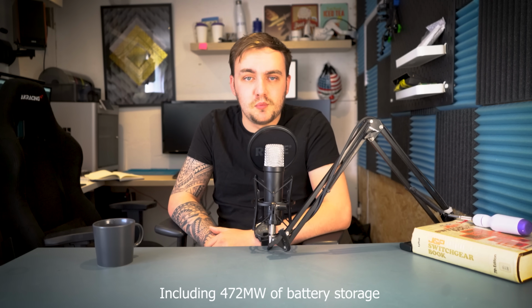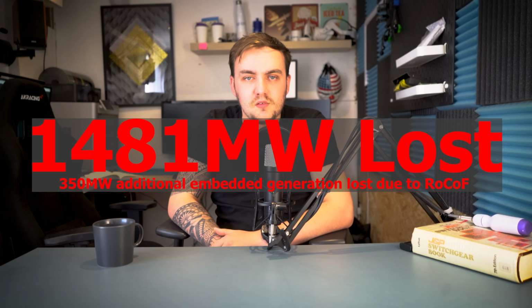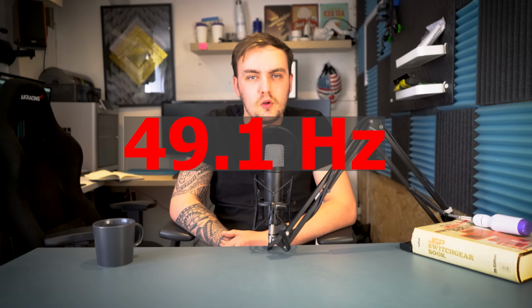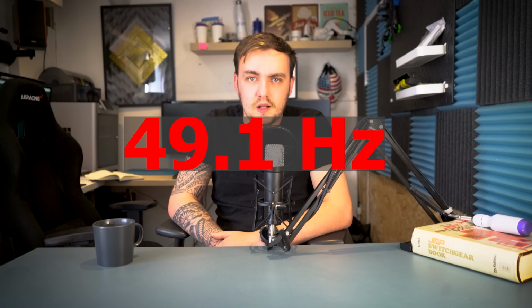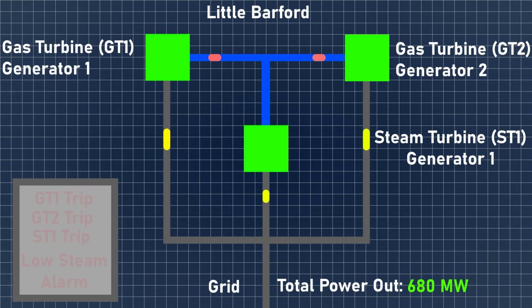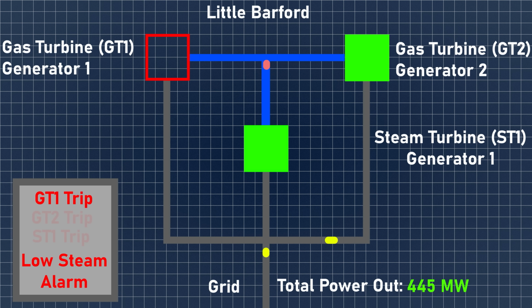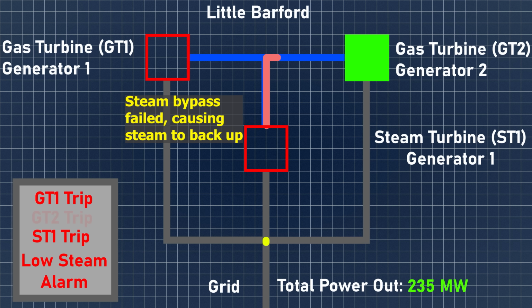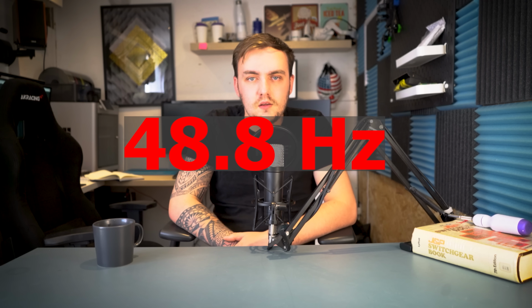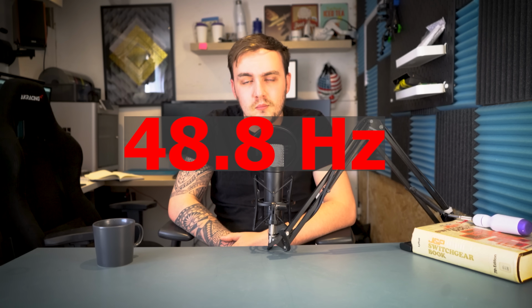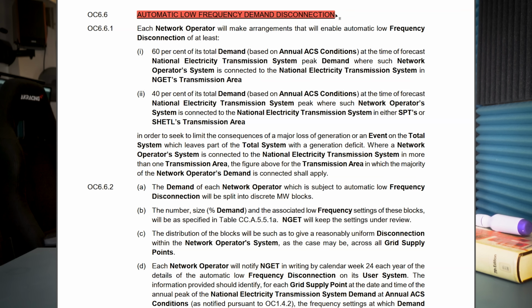The sudden imbalance pulled the grid frequency down sharply. All fast responses activated, but the system had to absorb a total generation loss of 1,481 megawatts, pulling the frequency down to around 49.1 Hz, dangerously close to critical levels. Then, another turbine at Little Barford tripped, removing another 210 megawatts. This final shock pushed the frequency down to 48.8 Hz, the trigger point for automatic load shedding. That's when the Low Frequency Demand Disconnect Scheme, or LFDD, activated.